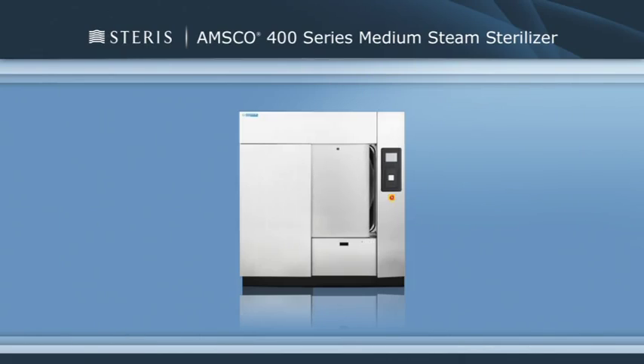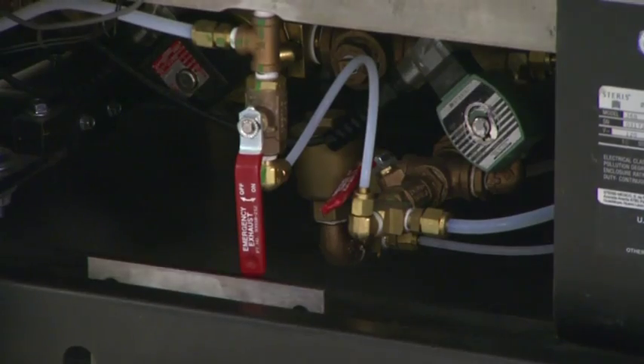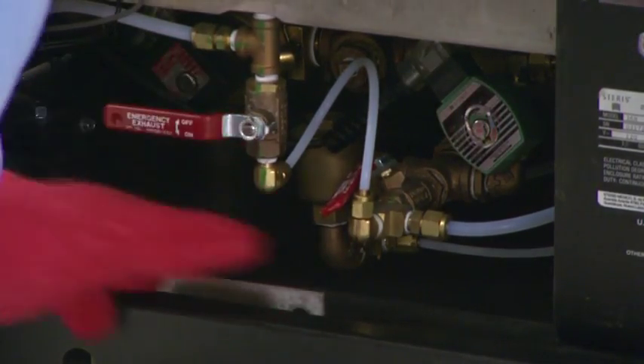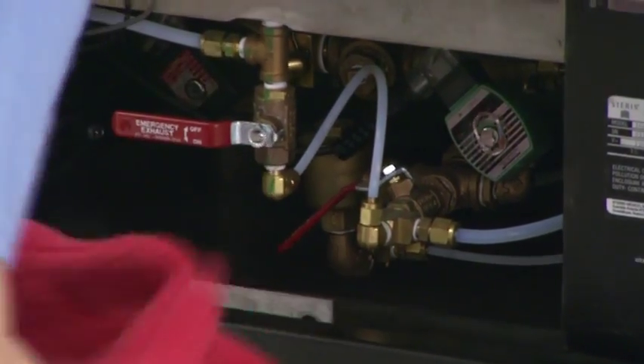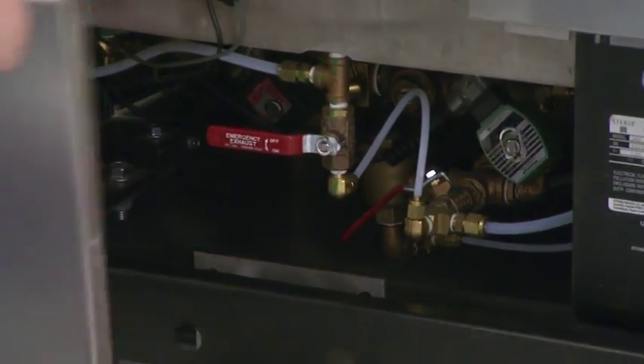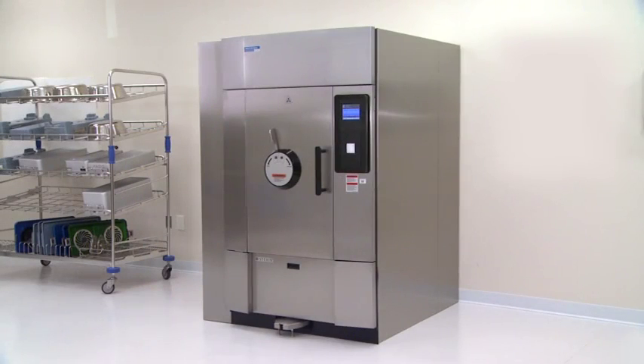To open sliding door units, once the door seal has been compressed, push the door in the normal direction of travel to open. The door slides stiffly, so be prepared to push hard. Once the door is open, close both emergency exhaust valves. Do not use the sterilizer until a qualified service technician has examined the unit. Further use without attention may damage the sterilizer.